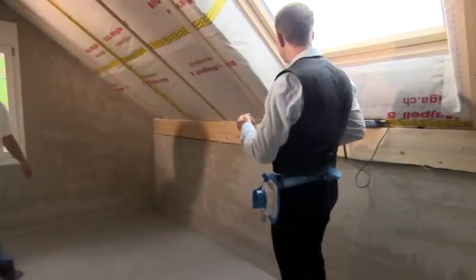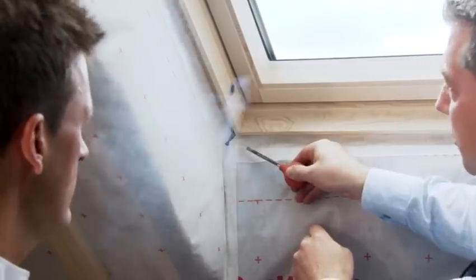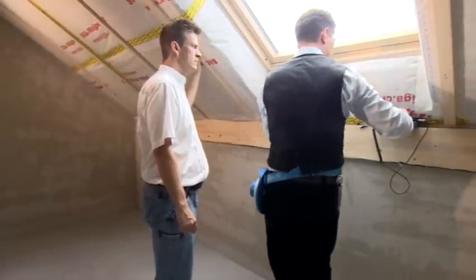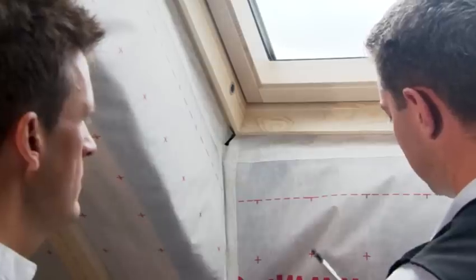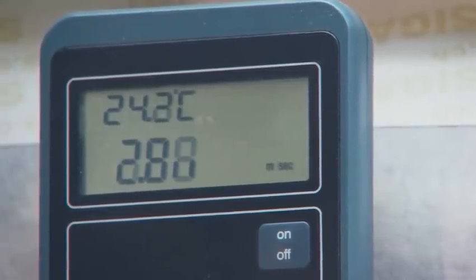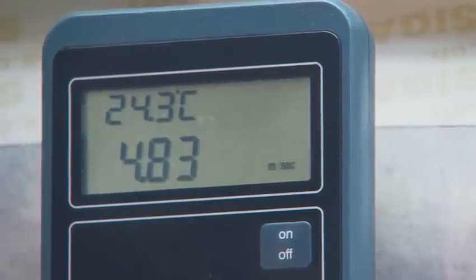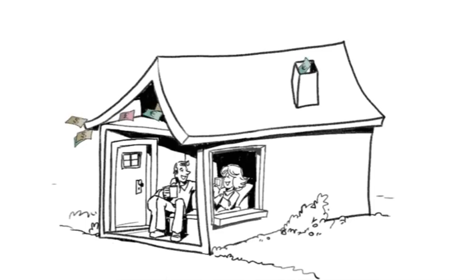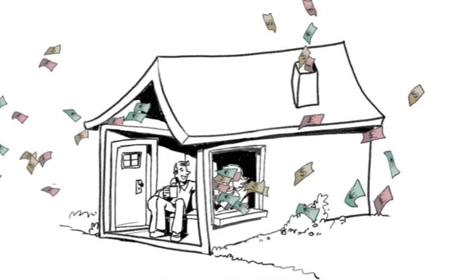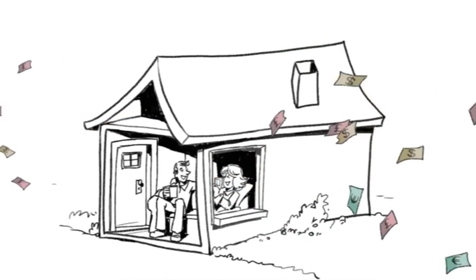Smoke escapes in the area of the skylight. It is not the skylight itself that is leaky, but the joint between the vapor control layer and the skylight frame. Using a smoke tube, leaks can be detected and air flows can be made visible. A thermal anemometer is used to measure the speed of the incoming air. We perceive inflowing air with a speed of more than 0.2 metres per second as unpleasant. It feels drafty. Cold drafts cause high heating bills. Up to 30% of heat can be lost through leaks.